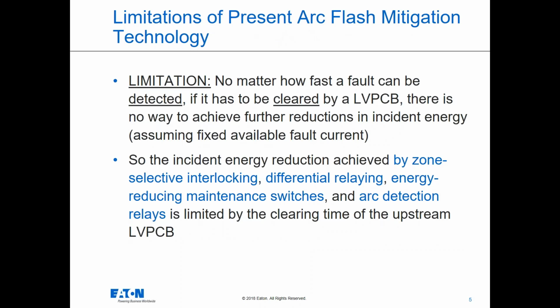No matter how fast I can detect that fault, regardless of what method I'm using to detect it, there's going to be a delay and no further way to achieve a reduction in incident energy because I can't make the breaker physically faster. So if I'm looking at the NEC and I'm looking at my 240.87 rules, they give me a lot of different methods by which I can mitigate arc flash energy: zone selective interlocking, differential relaying, energy reducing maintenance switches, arc detection relays, light detection systems, even adjusting the instantaneous on circuit breakers with the new 2017 NEC are all available as methods.